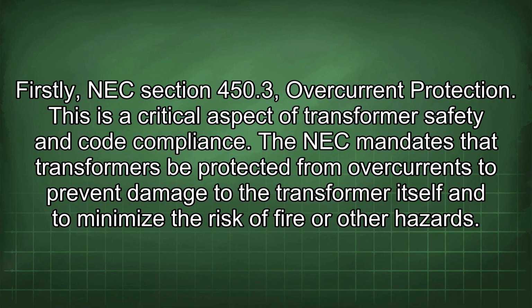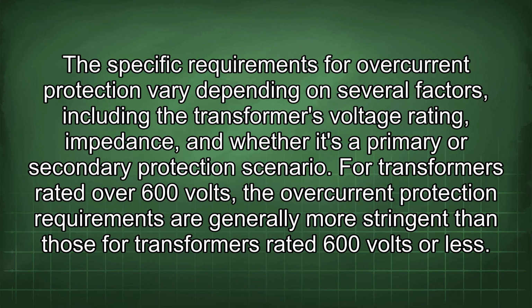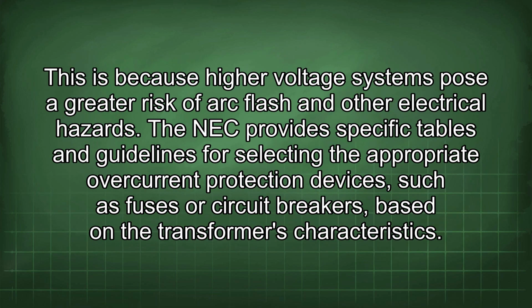The NEC mandates that transformers be protected from overcurrents to prevent damage to the transformer itself and to minimize the risk of fire or other hazards. The specific requirements for overcurrent protection vary depending on several factors, including the transformer's voltage rating, impedance, and whether it's a primary or secondary protection scenario. For transformers rated over 600 volts, the overcurrent protection requirements are generally more stringent than those for transformers rated 600 volts or less. This is because higher voltage systems pose a greater risk of arc flash and other electrical hazards.